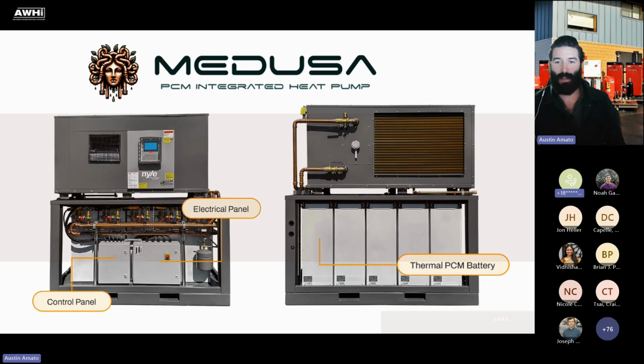Each one of the modules has outfitted on it multi-purpose service valves. Those multi-purpose service valves are outfitted with a union, an isolation valve, and a hose bib. The hose bib's there so that we could flush the open loop side of the heat exchanger, providing easy service for a technician.